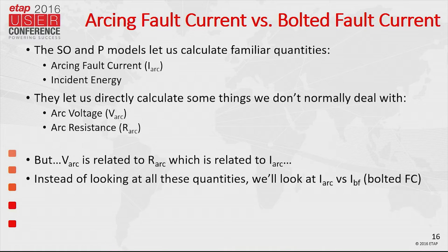What we did look at, a couple of things, arcing fault current versus bolted fault current was one of the big ones. Of course, there's a couple of ways that this is important. One, this helps us determine how much power we're actually going to be delivering to that load. The arcing current, of course, depends on the arcing voltage. Are we close to impedance matching? Are we a long way away from it? It gives us an idea of where we're at in terms of the power. And of course, the arcing fault current is very important because it also helps us determine what the clearing time is going to be.